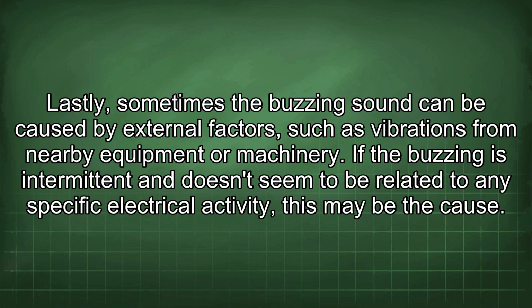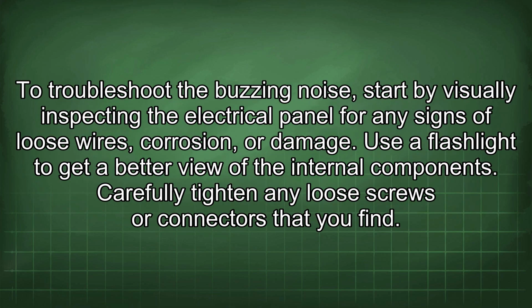Lastly, sometimes the buzzing sound can be caused by external factors, such as vibrations from nearby equipment or machinery. If the buzzing is intermittent and doesn't seem to be related to any specific electrical activity, this may be the cause. To troubleshoot the buzzing noise, start by visually inspecting the electrical panel for any signs of loose wires, corrosion, or damage. Use a flashlight to get a better view of the internal components.